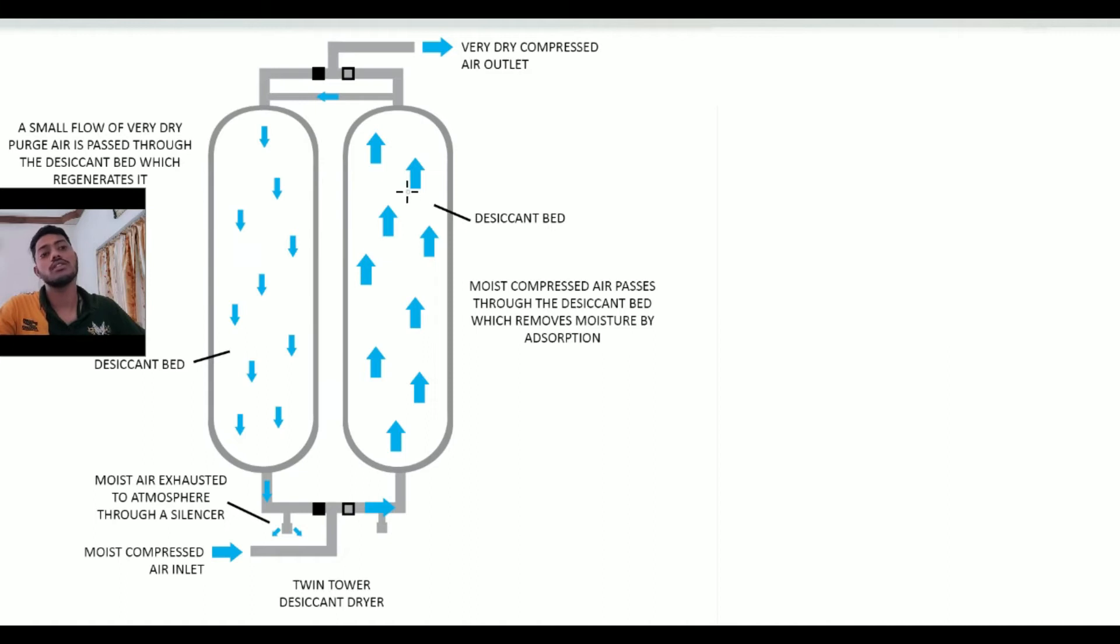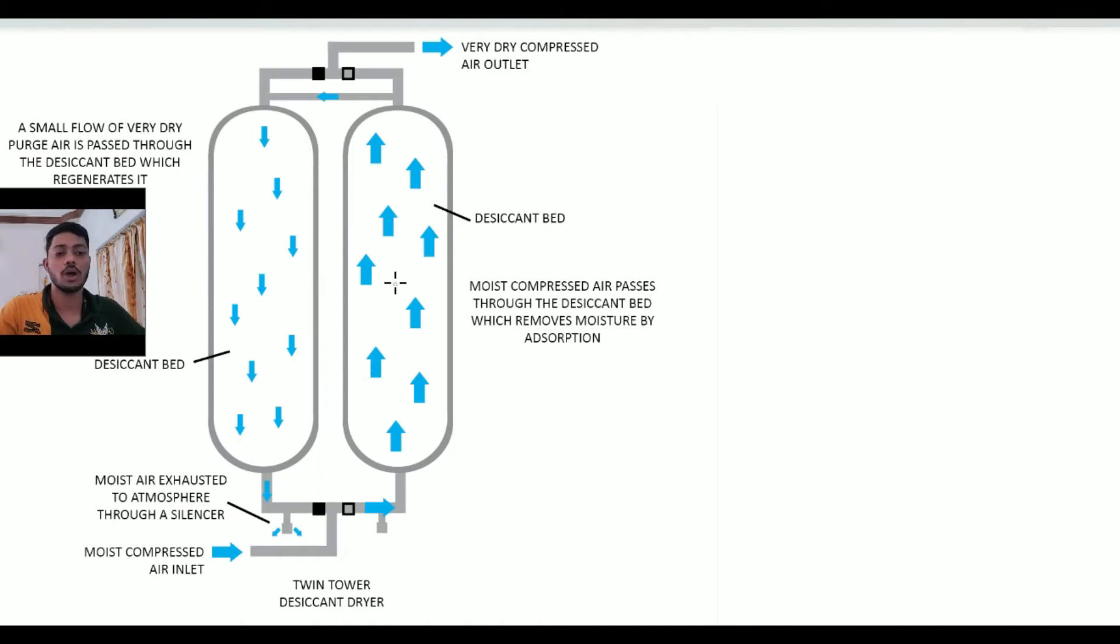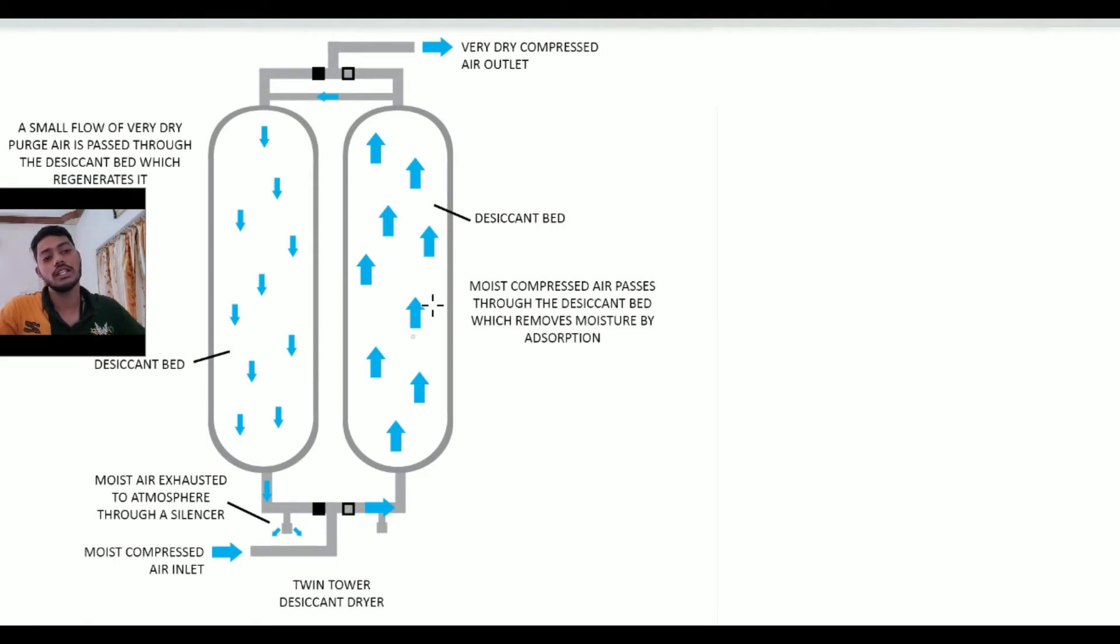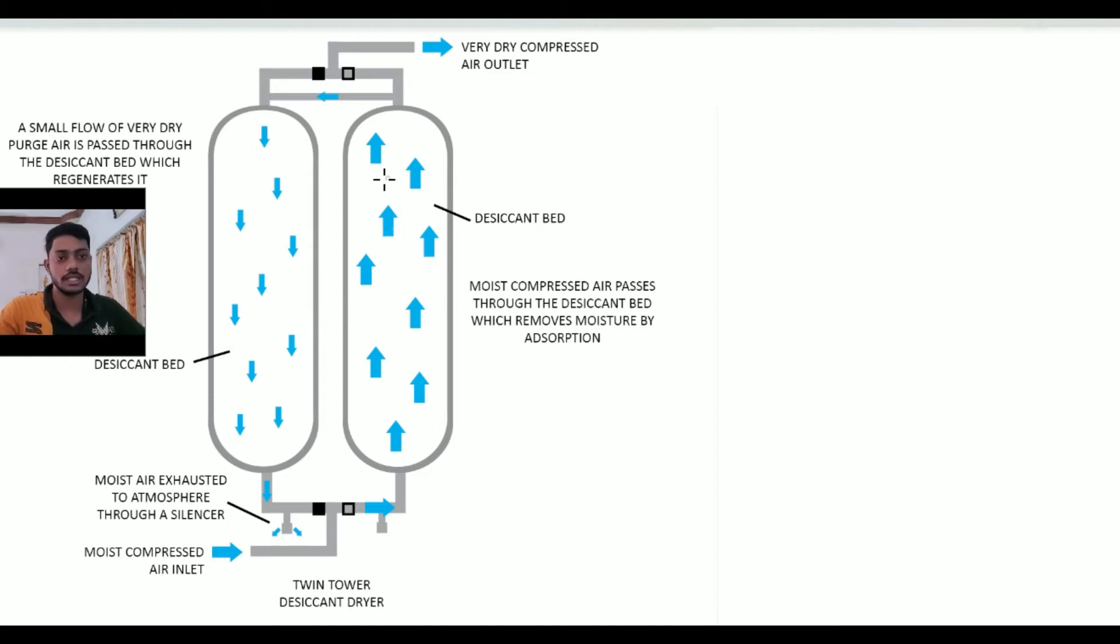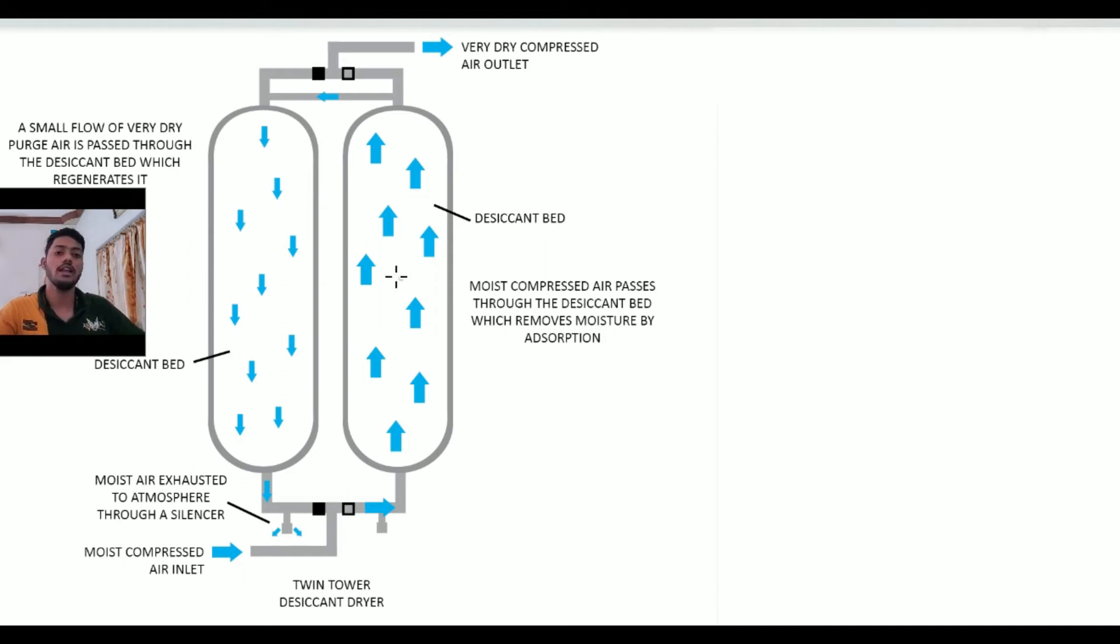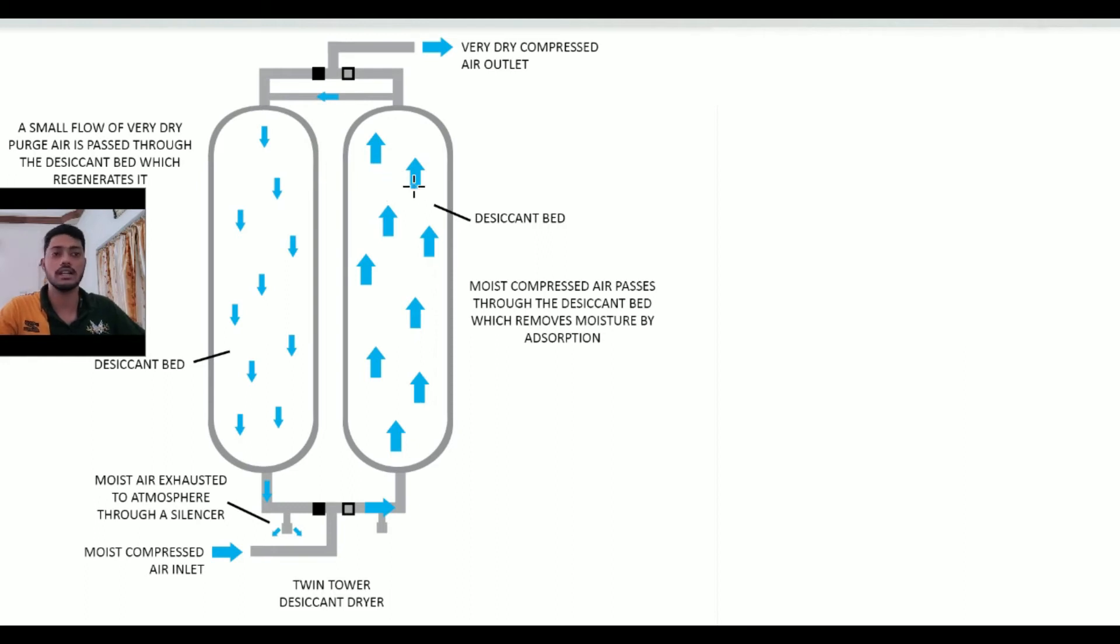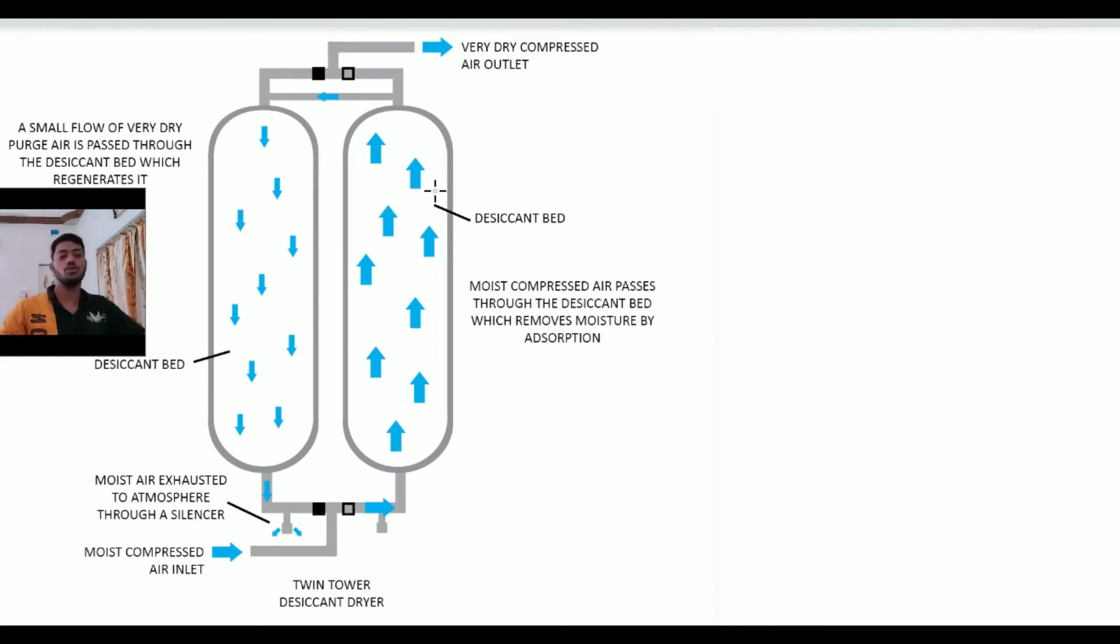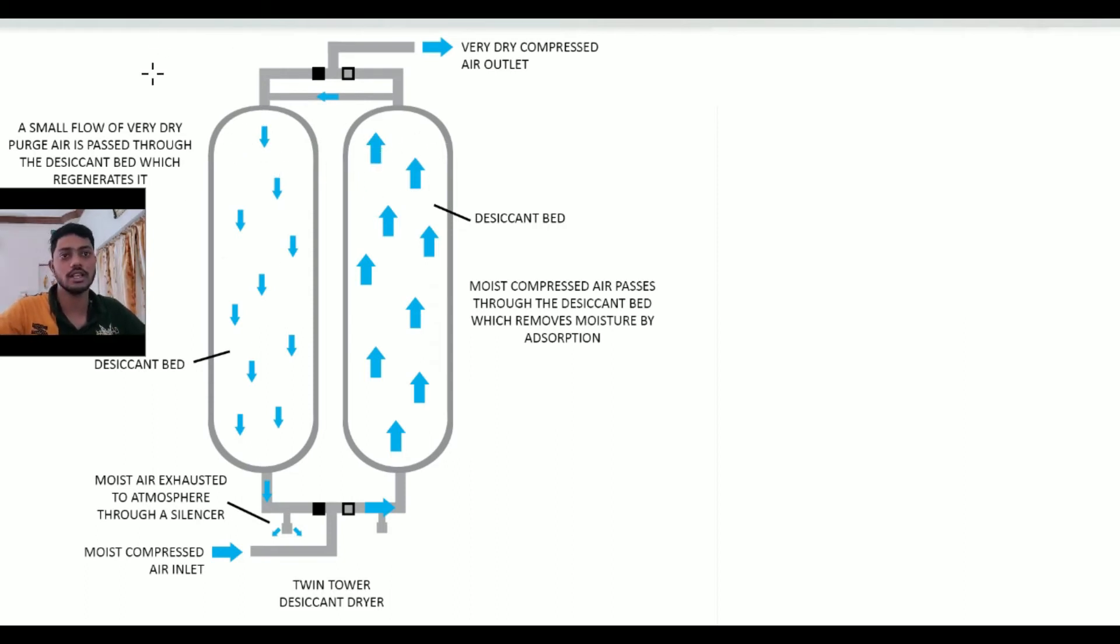Why? Because once this cylinder is processing the air drying and absorbs all air moisture to desiccant molecules, ultimately these desiccants are saturated with water vapor or air moisture. If these desiccants are saturated, then the upcoming wet compressed air cannot get dried because these desiccants are already saturated. Here we need the regeneration process to interact with this second cylinder.